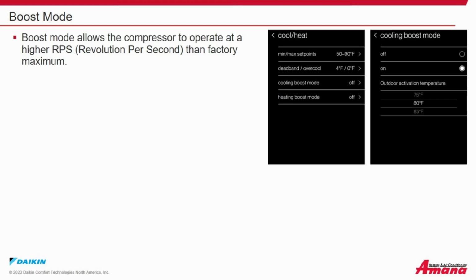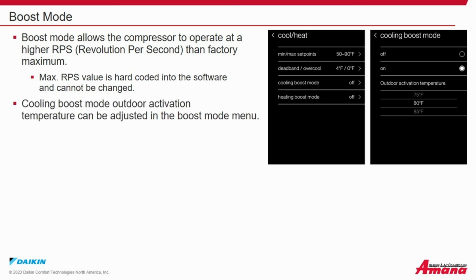Boost mode. Boost mode allows the compressor to operate to a higher RPS, or revolutions per second, than factory maximum. Maximum RPS value is hard-coded into the software and cannot be changed. Cooling boost mode outdoor activation temperature can be adjusted in the boost mode menu.